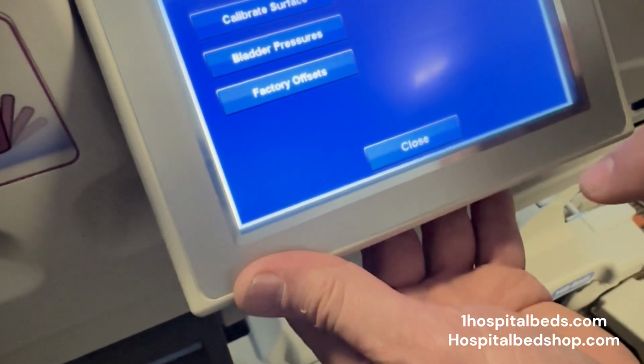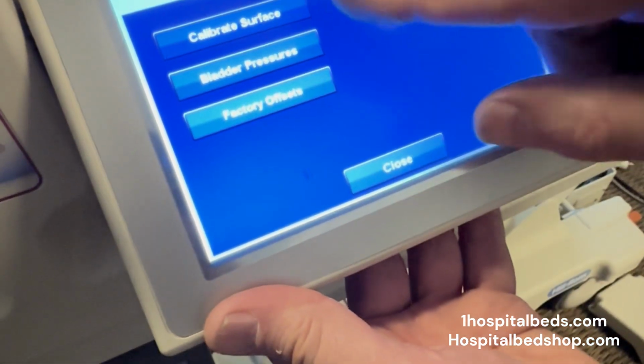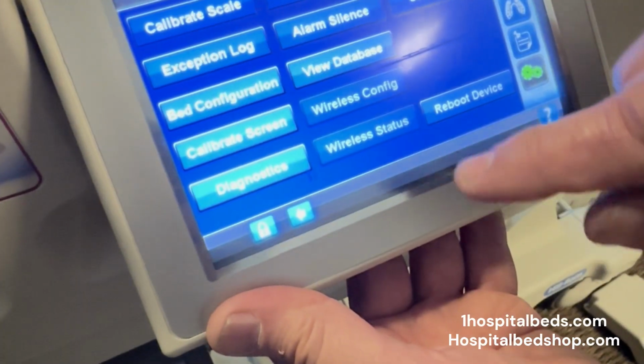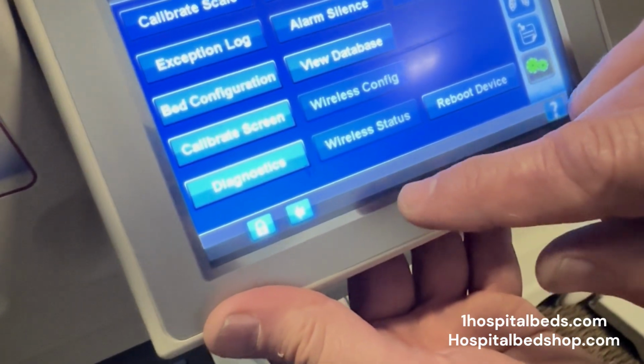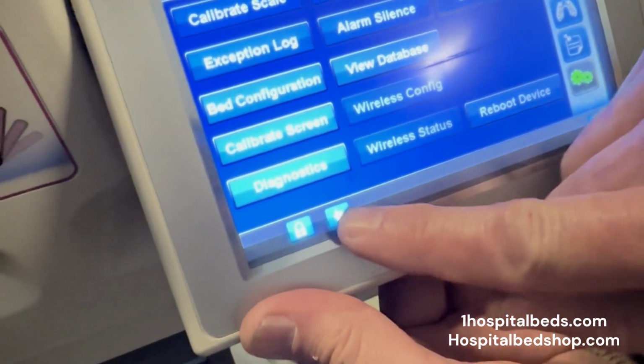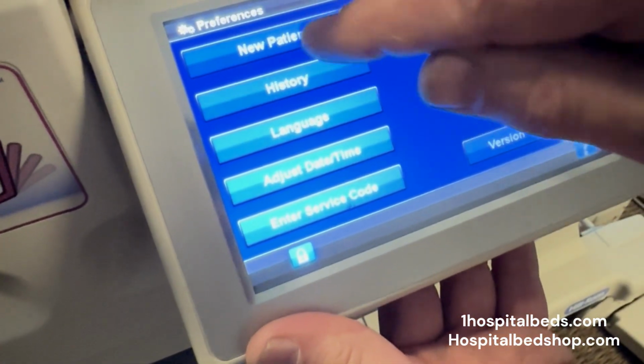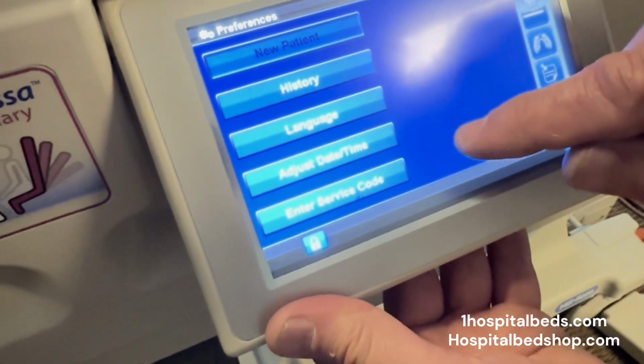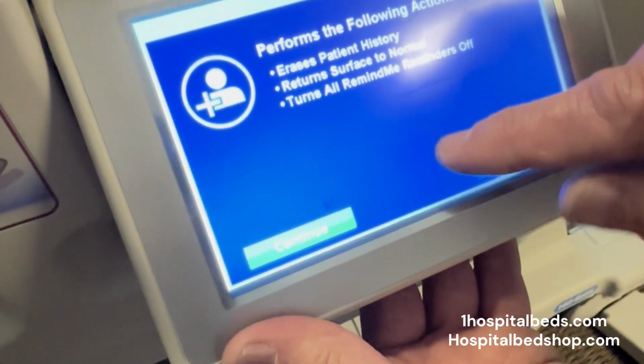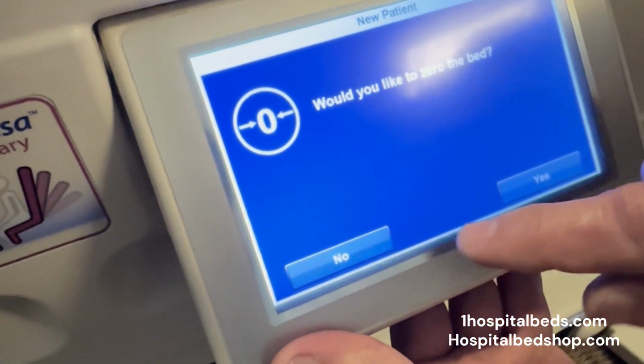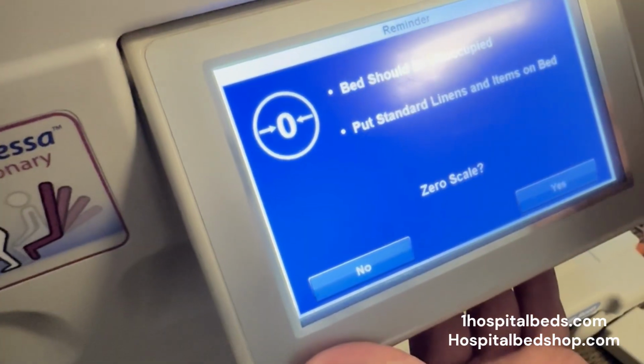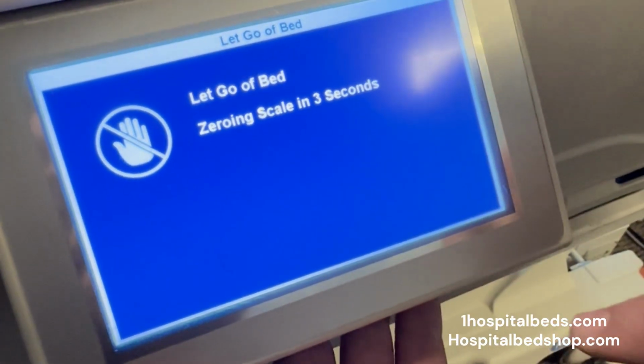But this is something that we see all the time, where whoever was doing the work on the bed previously was not pulling out and cleaning the filter. And one of the things you'll see go wrong on these beds is the blower going out. And the blower obviously is going out because whoever was doing the service on it was not going the extra mile and not taking that piece off and not cleaning out that filter.